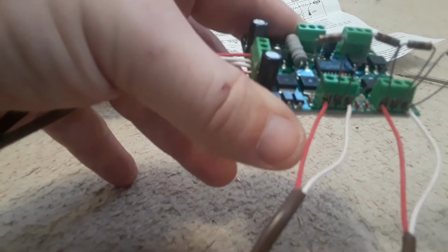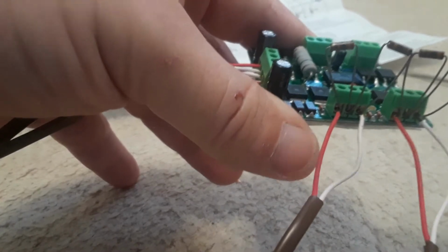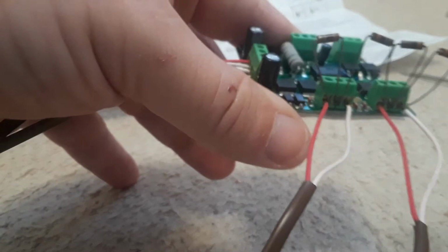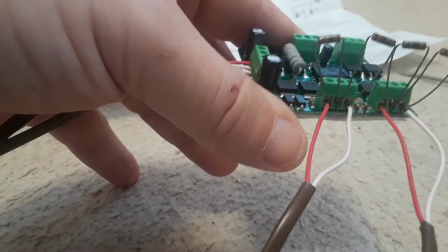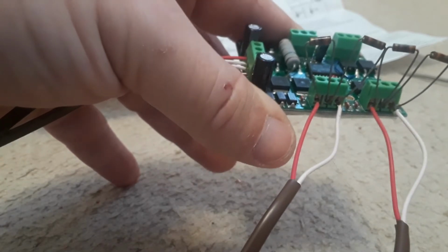When you wire the other side, make sure that you do it right, because like some electronics, they're mirrored on the other side. This isn't. All the 1s are on that side. All the 2s are on that side, even up here. So wire accordingly. Now we're going to take this downstairs and mount it and then wire it up to the system.